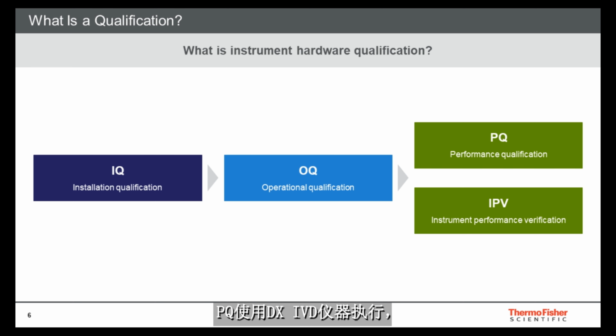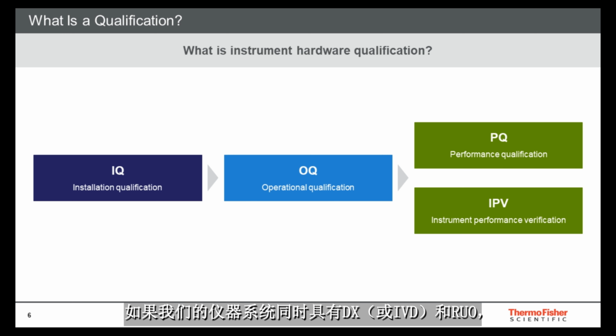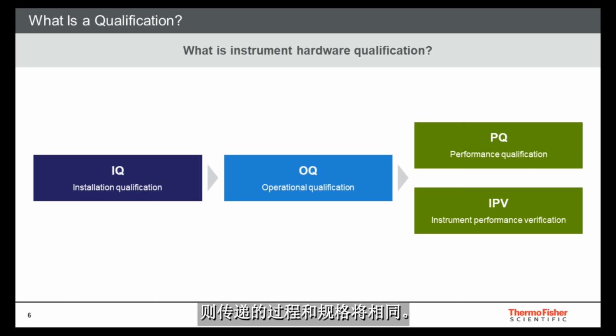The PQ is performed with the DX IVD instrumentation, and the IPV, or instrument performance verification, is performed with the RUO, or research use only instruments. To be clear, for our audience, this is strictly Thermo Fisher Scientific nomenclature to differentiate our instrumentation and the qualification services. For all intents and purposes, they are equivalent. Where we have instrument systems as both DX or IVD and RUO, and the standard for performance is the same, the process and specification for passing will be the same. All three components make up a qualification protocol. We will be speaking in more detail for each of these qualification components, as well as the difference between a hardware product PQ and a workflow process PQ.